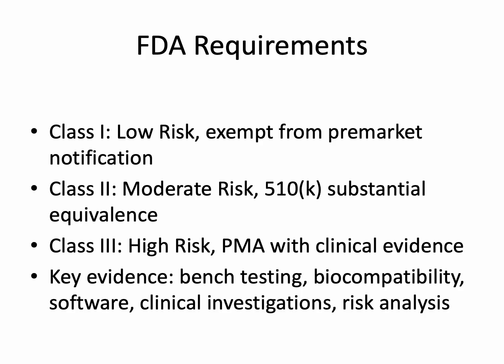Key evidence includes non-clinical laboratory studies, biocompatibility testing, software validation if applicable, clinical investigations, and risk analysis aligned with ISO 14971. Understanding these requirements ensures the testing strategy satisfies FDA expectations while mitigating regulatory delays.